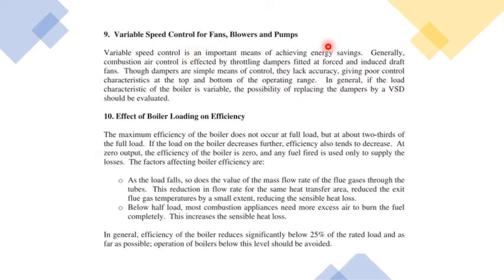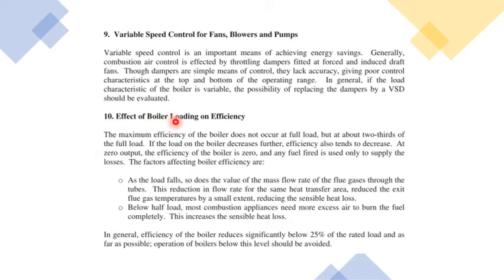The ninth point involves controlling fans, blowers, and pumps used as auxiliaries in the boiler using variable speed drives (VSD). By controlling these drives as per the actual air and water requirements, wastage is eliminated, leading to optimum supply and better overall boiler efficiency. The tenth point is the effect of boiler loading on efficiency — running the boiler at very low load leads to poor efficiency, so it should be run at an optimum load.